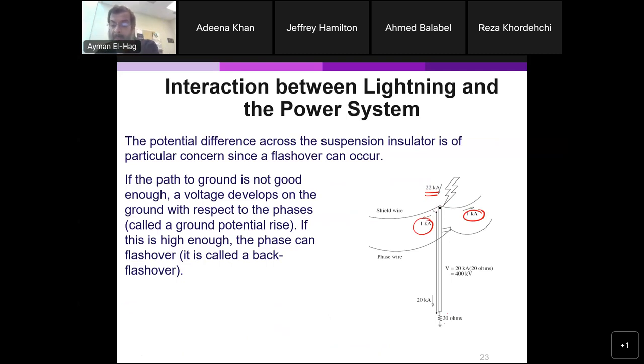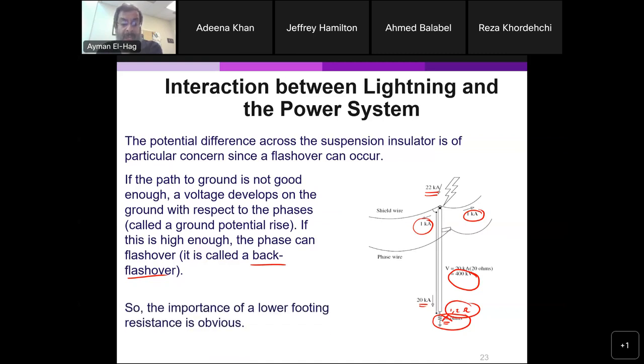But this will lead to a problem if we have a high foot resistance. If the foot resistance is high, multiplying it by the 20 kiloamps, you get 400 kilovolts across the insulator, and this will definitely lead to a flashover of the insulator. This is called a back flashover. So we want to have this be a very, very small value, 1 or 2 ohms only. Then, for something like a 20 kilovolt distribution or transmission line, it will be able to withstand such a high voltage, and no flashover will happen. So it's extremely important to lower the footing resistance to avoid such a problem.